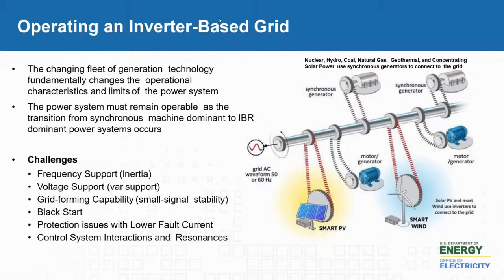But we also need to be able to support voltage and reactive power. We also need grid-forming capability, basically the ability to generate the right frequency, not just follow the frequency of the grid, but to be able to dictate what the frequency should be. And then black start, for when the system falls apart in unlikely but possible events, if you need to bring it back up.